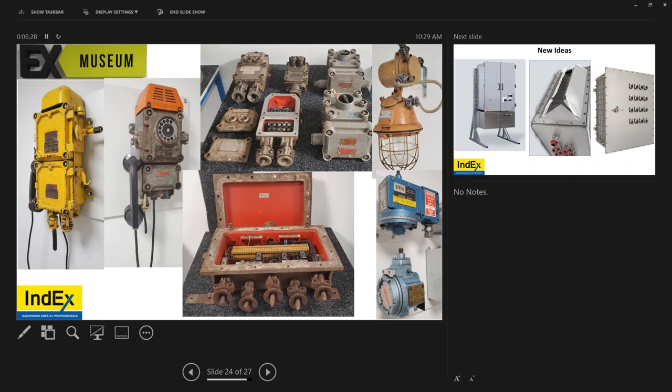If an EXD equipment is being modified to include additional terminals, okay, if you want additional terminals and it's approved by the certificate and IOMs, go for it. Same size, you follow their tables. It's usually in the annex or in the conditions of use. Now, if you're doing something different, no, don't do that. It's unsafe. Call the manufacturer, ask them for their solution.